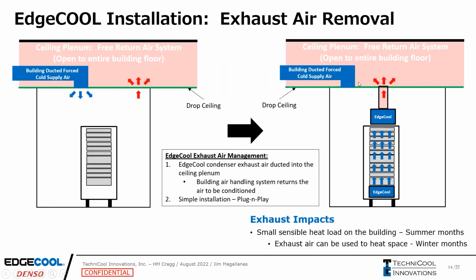Oops, excuse me. This is how it's going to be looking most of the time. About 90% of the time, the racks are inside a small room. They maybe have ducted forced cold supply air coming into the room, and then they have a free return air system. We'll put in the EdgeCool unit. We'll put some ducting up into the drop ceiling, and then put the warm air up there. The building air handling system will take that back and condition it. That's a very simple installation, and that's going on most of the time.